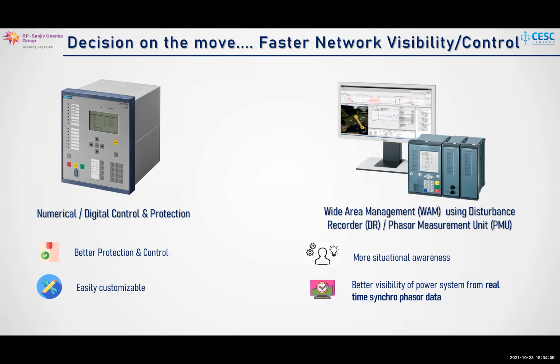You can take decisions faster. You can get all this data on your mobile even, while the operating engineers, for a better work-life balance, may be enjoying a movie or having dinner at a restaurant, and the protective devices may on their own push notify the pre-assigned mobile phones or tabs that a protective device has operated in some portion of the network say the red phase to earth fault has occurred, so much kiloamperes is the fault current, and so many milliseconds it took to isolate itself. So the operating engineer knows which part of the network is faulty and may take corrective action, restore the other portions of the network, and so on.